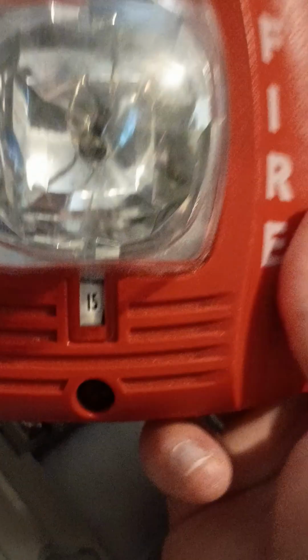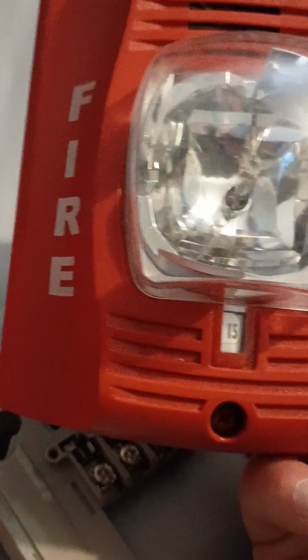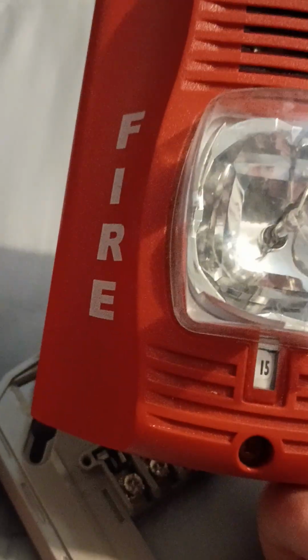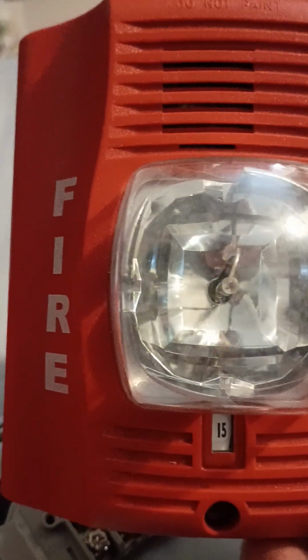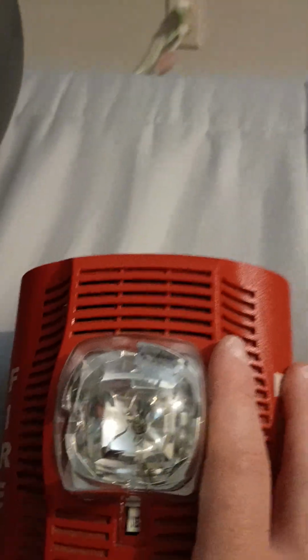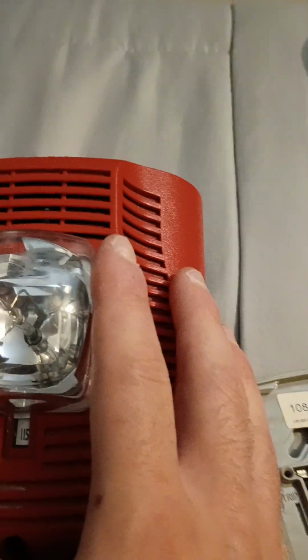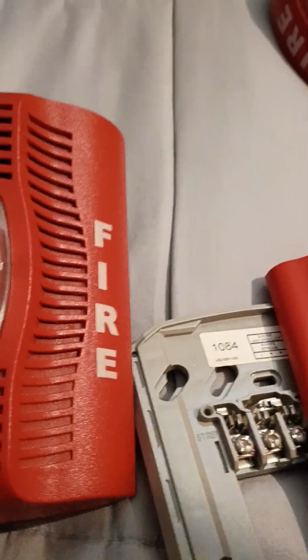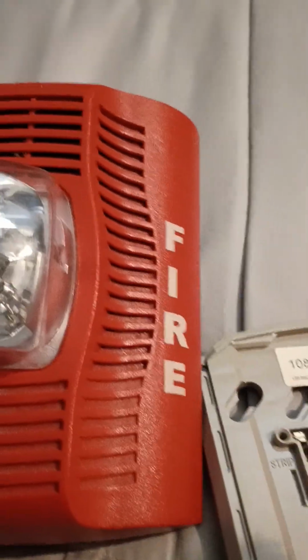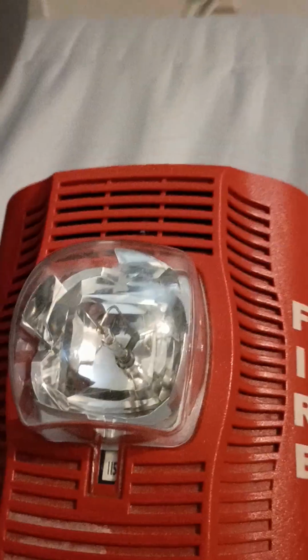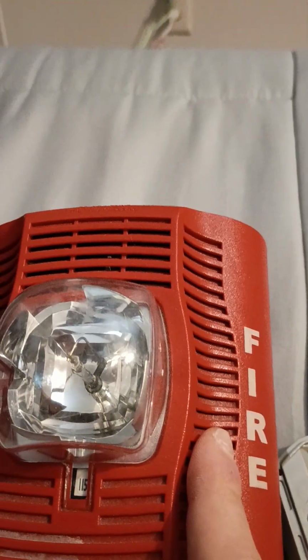So that's the System Sensor P2R horn strobe. Now basically horn strobes you see in low-rise to mid-rise buildings. So low-rise buildings would be 1 to 4 stories high, and mid-rise would be 5 to 9 stories high, and high-rise would have these kind of devices. Here's the fun fact, guys. Even though low-rise or mid-rise buildings tend to take more horn strobes, if you had a large space that could hold a capacity of over 1,000 plus people, and there's a lot of people, you would actually install voice-evac systems.